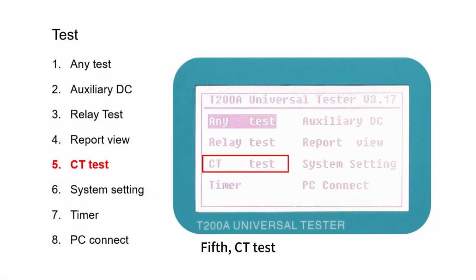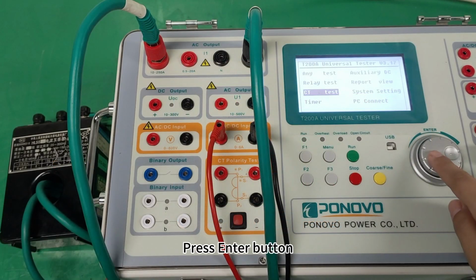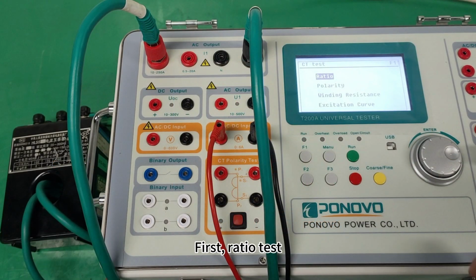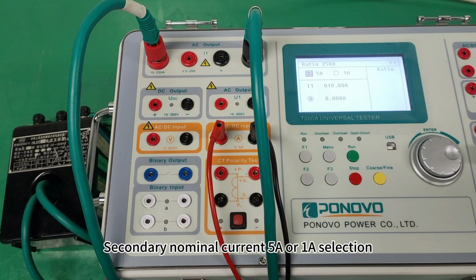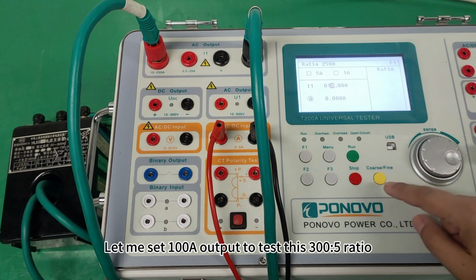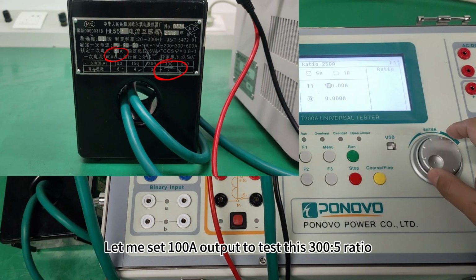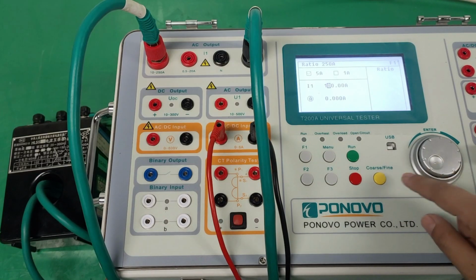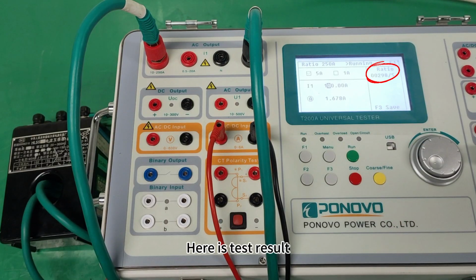Fifth, CT test. Press Enter button. First, ratio test. Secondary nominal current 5 amperes or 1 ampere selection. Let me set 100 ampere output to test this 300:5 ratio. Press Run button. Here is test result.